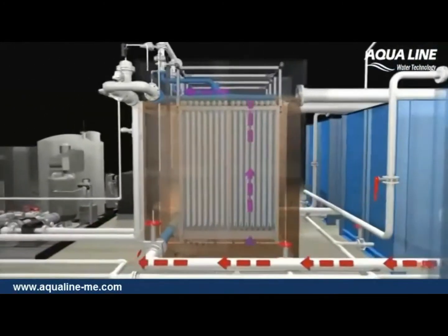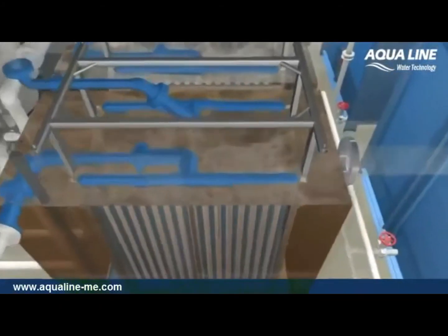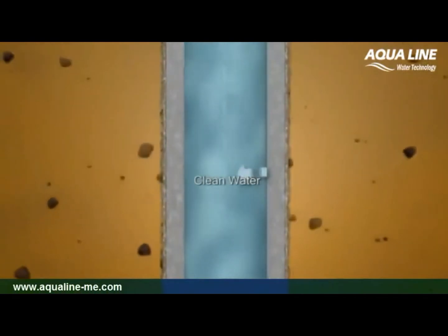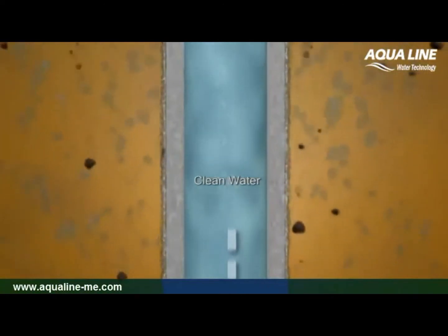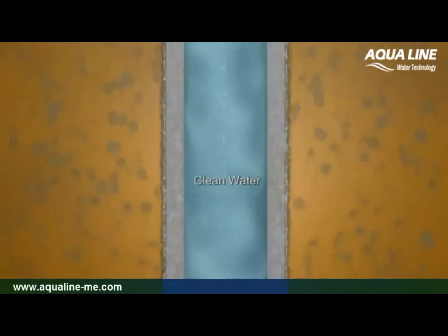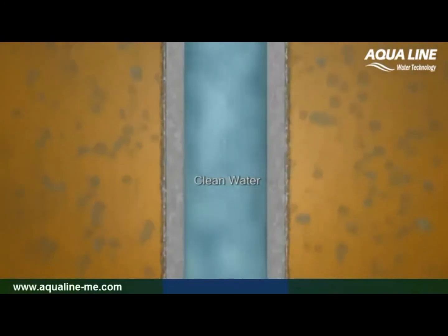Puron membrane modules are fully submerged in the mixed liquor inside the membrane tank for direct outside to inside filtration. The membrane modules are made up of hollow fibers with a nominal pore size of 0.05 micron. These robust, reinforced second-generation hollow fibers are cast on an internal reinforcing braid to overcome the fiber breakage problems typical of first-generation systems. The free-floating tips of the hollow fibers in the single header design of the Puron module also reduce breakage by placing less mechanical stress on the fibers than in modules that use a double header design.